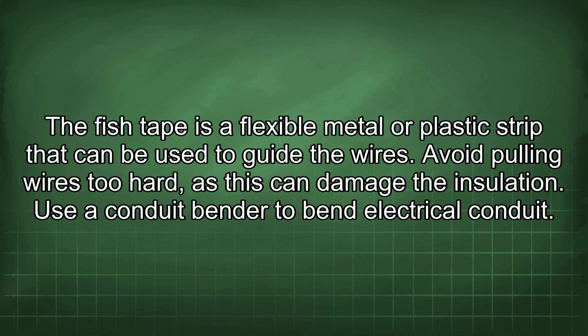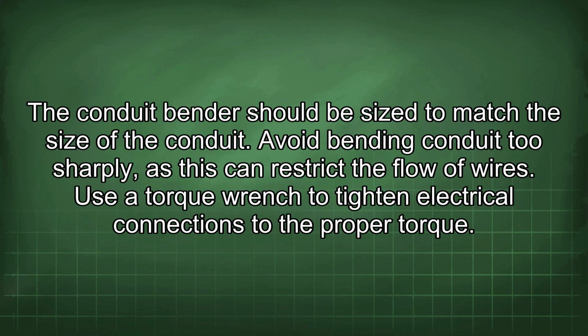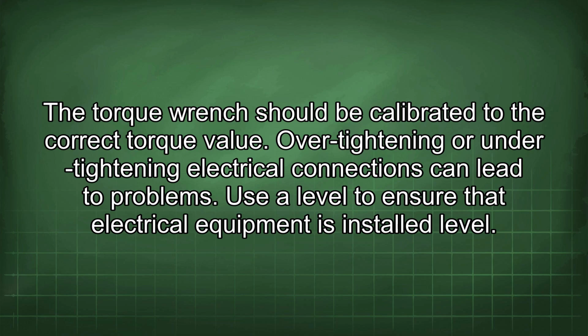Use a conduit bender to bend electrical conduit. The conduit bender should be sized to match the size of the conduit. Avoid bending conduit too sharply, as this can restrict the flow of wires. Use a torque wrench to tighten electrical connections to the proper torque. The torque wrench should be calibrated to the correct torque value. Over-tightening or under-tightening electrical connections can lead to problems.